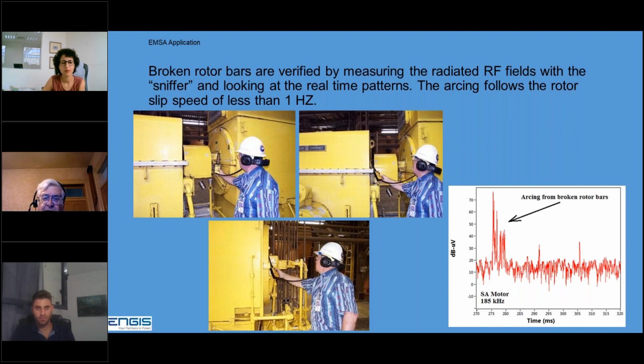Also with this, you can check if you have a coupling misalignment. If we had steady arcing and it was on the outboard bearing, the inboard bearing, and the other side of the coupling, then you have a misalignment and that coupling needs to be inspected.